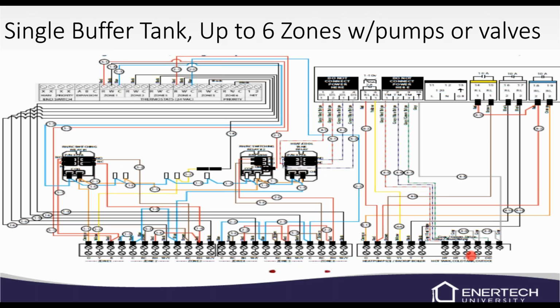This is a single buffer tank up to 6 zones with pumps or valves. So a lot of times we've got a system pump for our zones, and then we're using a system pump and then zone valves. You can also put zone pumps at each zone and do it that way, and this would be the setup here on that as well. This would be using HBX controls as well.